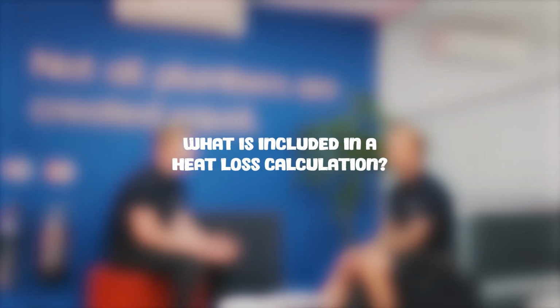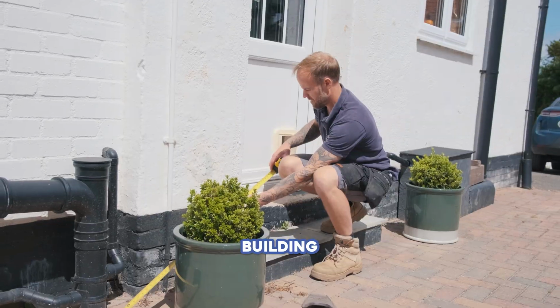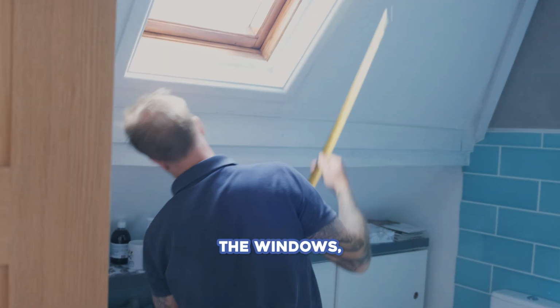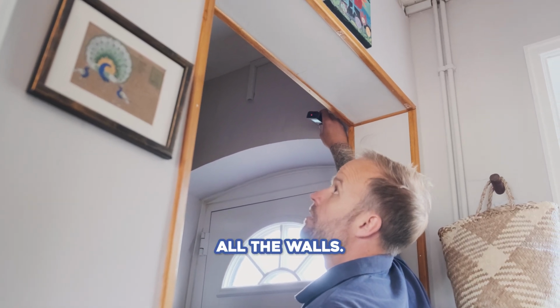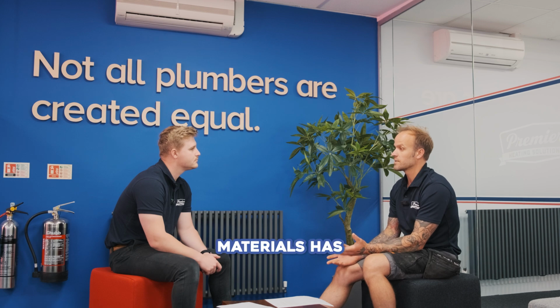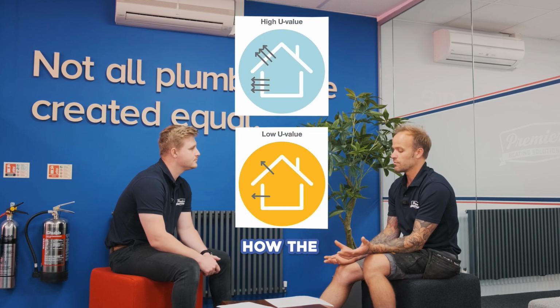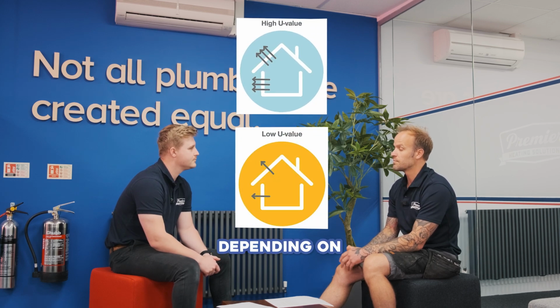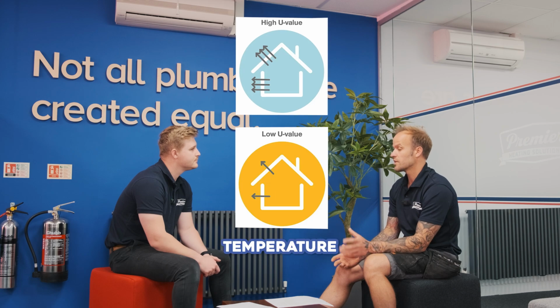So what is a heat loss calculation? A heat loss calculation is a method we use to determine how much heat is lost through your building. What is included in a heat loss calculation? With the calculations, we're really looking at the building fabric, the roofs, the windows, doors, all the walls, because each of those materials has a U value, which is how the material conducts heat depending on the difference between the temperature inside the property and outside the property.